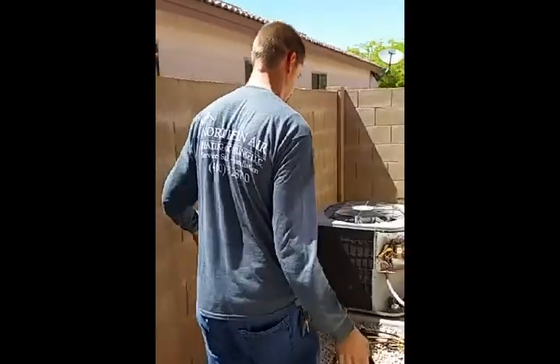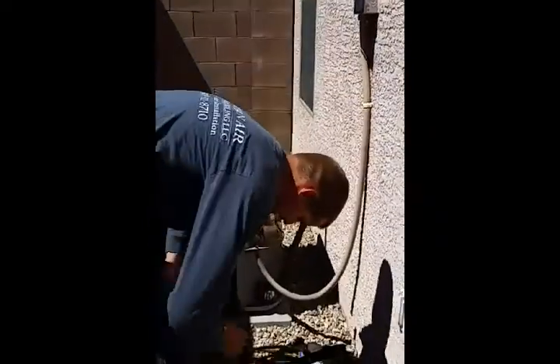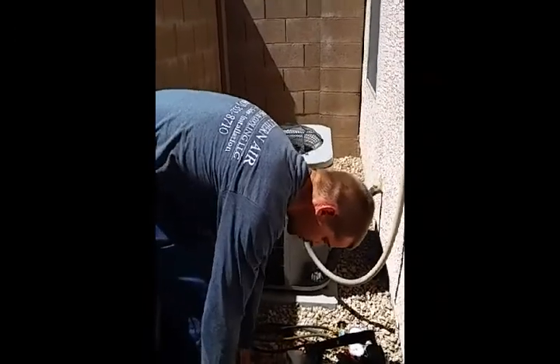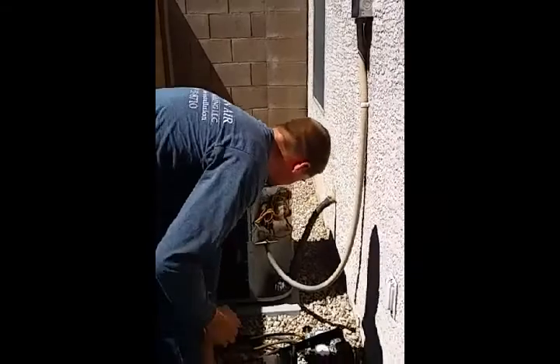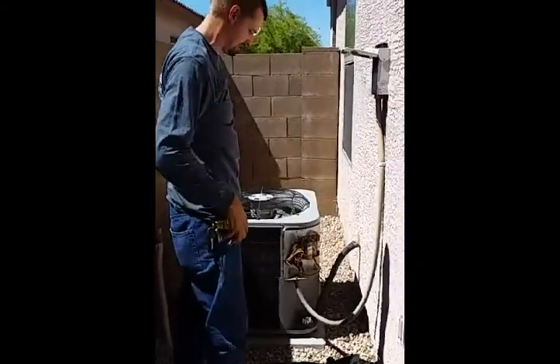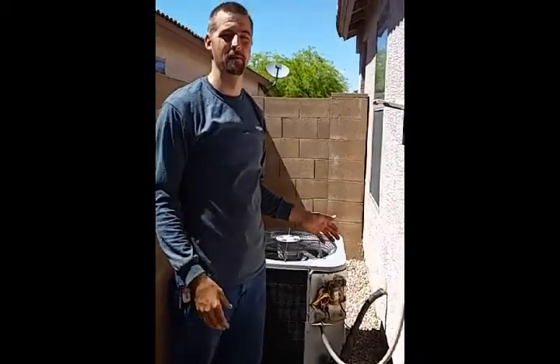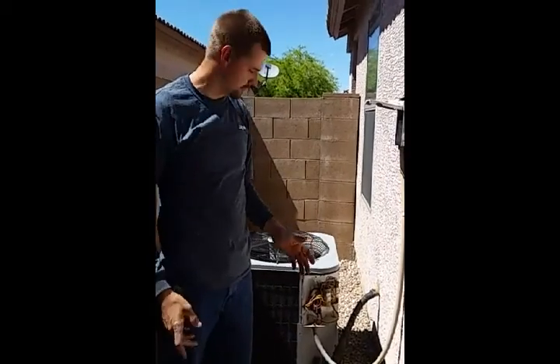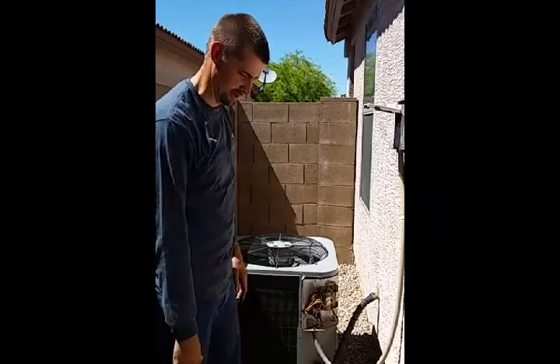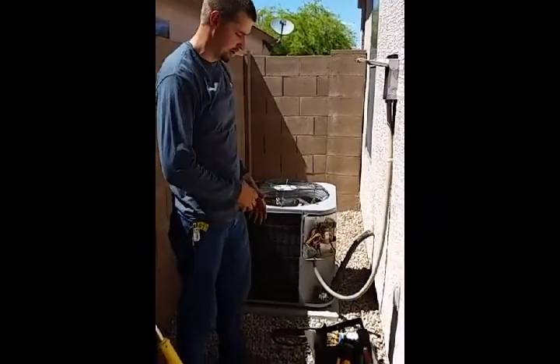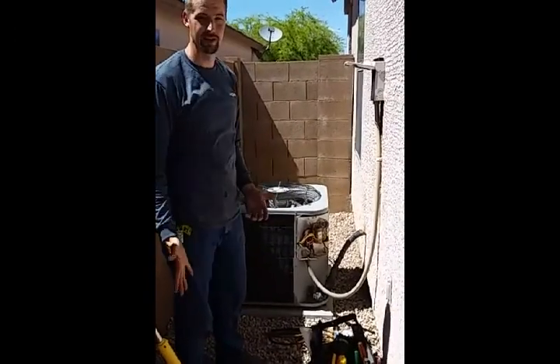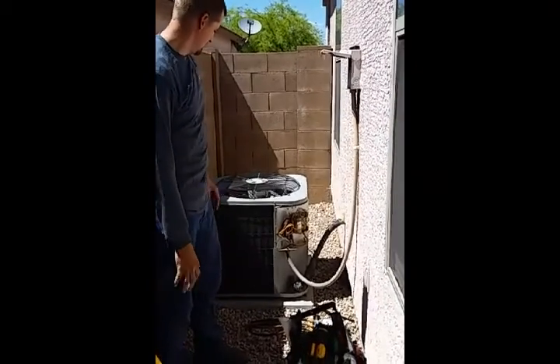The only thing with system tune-ups is they're going to charge you, say, a $159.99 fee no matter what. So what I like to do is find out if the system is running okay, do my preliminary checks, and then inform you after of all the issues, like I said earlier. And here we'll just basically go over a few things. Right now, this is a piston style metering device in the indoor system. So what I will be focusing on is superheat readings. Usually you want to do both. But today, because we're recording a video, we'll just do the superheat readings and make sure our pressures are okay as well. So we'll get started on that.